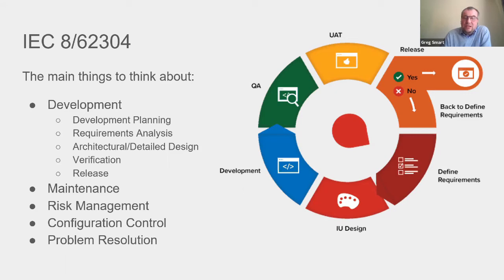You will need to demonstrate a process for verification. And I want to just clarify for a moment the difference between verification and validation. So verification, I like to say, is have we built the product right? And validation is, have we built the right product? So by that I mean, verification is looking at, have we built the product right? Have we gone through the right process? Can we show that what we've got at the end of our development process is what we wanted at the start? And classically, the way you do that is to look at traceability.